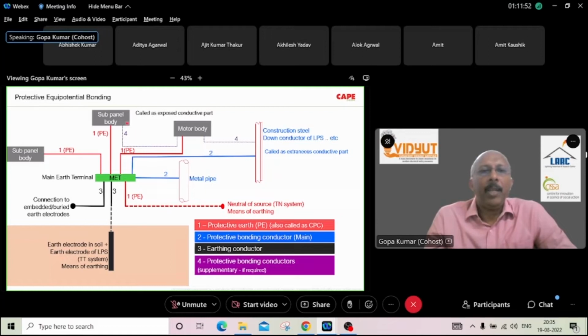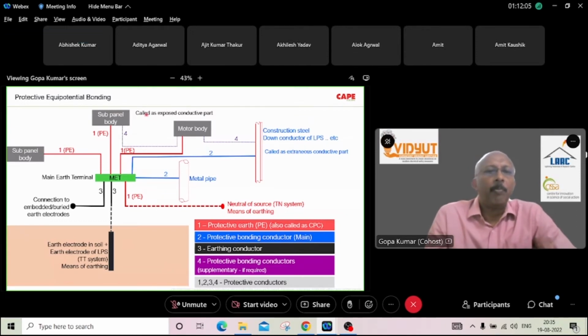Now, at the far end of your electrical installation, you should also have a protective measure called supplementary equipotential bonding. You can see here, all these connections together are called protective equipotential bonding. In every electrical installation, it is a mandatory requirement that protective equipotential bonding must be made.